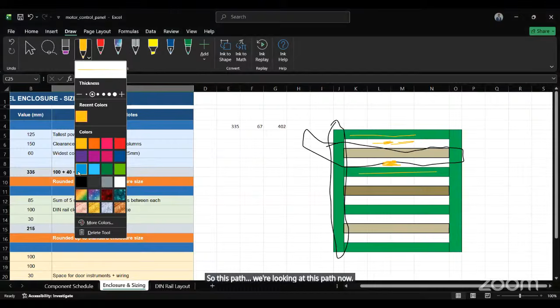So if we're having this now, the sum of the 5 components plus the 15 gap. On the DIN rail, if you remember from the last class, I explained that your DIN rail should always have at least 20% gap for expansion. You should leave room for expansion. So this part, we're looking at this part now, this part of the panel.